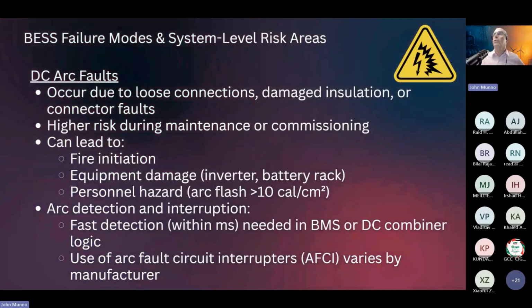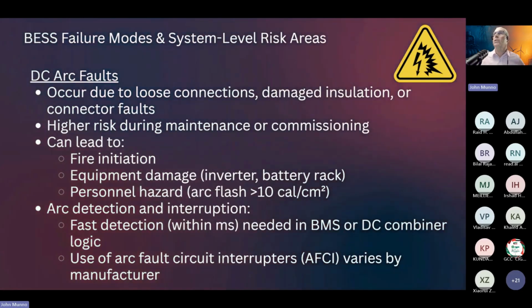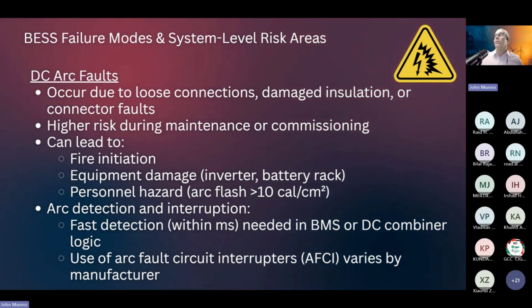All right, what else can go wrong? DC arc faults. What we see here are loose connections, especially the MC4 connectors and mismatched connectors, which is a problem in solar farms. But anywhere in the battery system, if we have loose connections or damaged insulation, we're going to start to see DC arc faults. And these can lead to fires, equipment damage and personnel hazard. We need to have arc detection and interruption. Within milliseconds, either in the BMS or in the DC combiner logic, we have to be able to shut down the battery so that we don't continue to cause an arc that just gets worse.